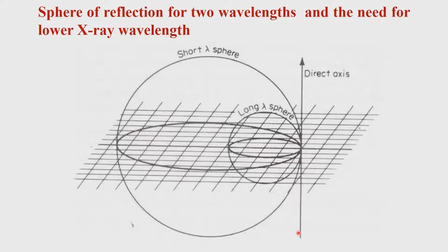Then the accessibility volume will anyway increase, but our measurement device and the way in which we design the experiment, the diffractometer construction, a mechanical device which is moving the arcs to measure the distances, and also the detector capability, limit the value at which we can collect the data. So normally it is recommended that we use wavelengths of that particular order which will resolve the distance between the two atoms. So the most preferred wavelength if we are using laboratory X-ray sources is molybdenum.